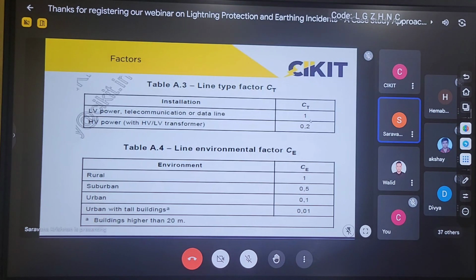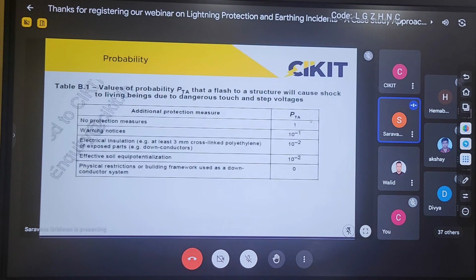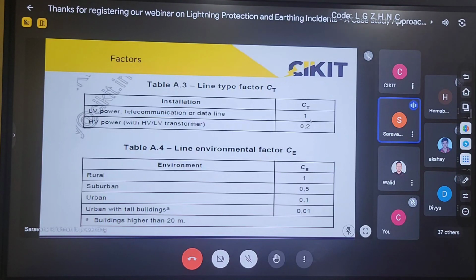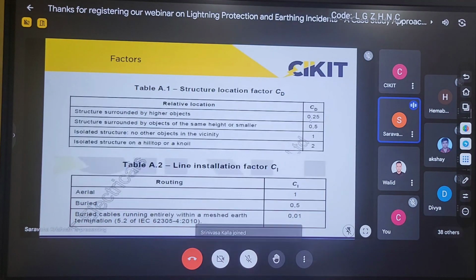So next is probability of damage. Up to the previous slide, we explained the parameters involved in the number of dangerous events per annum, NX. The second one is the probability. In the previous slides, we don't have any control over the parameters involved. For example, I don't have any control over the line environmental factor, or over LV power or HT power. If I want to take HT power, then my demand has to be higher. I cannot take HT power for lower power demands. I also cannot control the height of the structures surrounding my building.